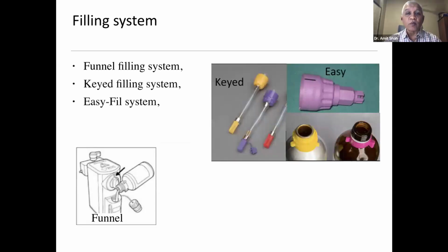The filling system, as I said earlier, was a funnel filling. So you open the vaporizer opening and directly pour the liquid with the help of a funnel. But then we realized it was creating problems. So we started making agent-specific designs where you cannot put the wrong agent into it. And then the leakage and the atmospheric leakage and the loss is also not there. So one was a keyed filling. Okay, this was a key which was made.